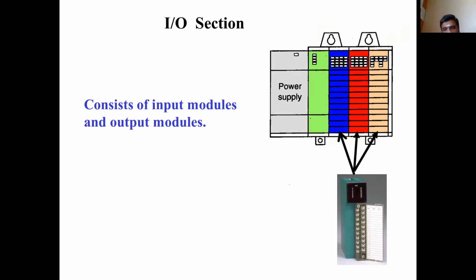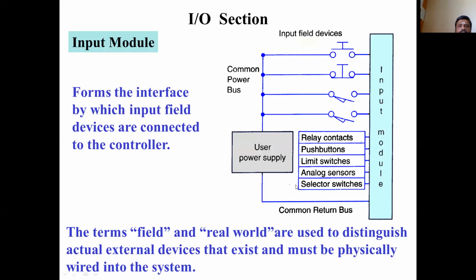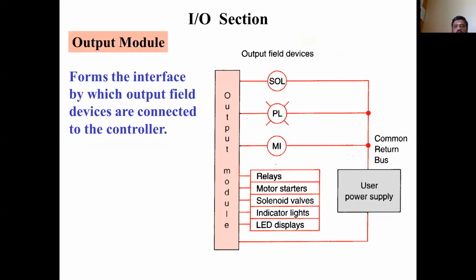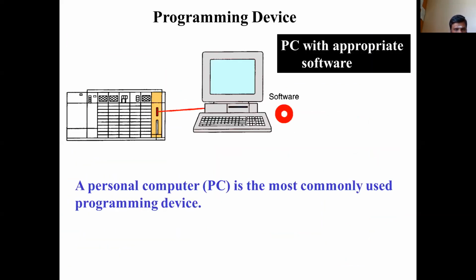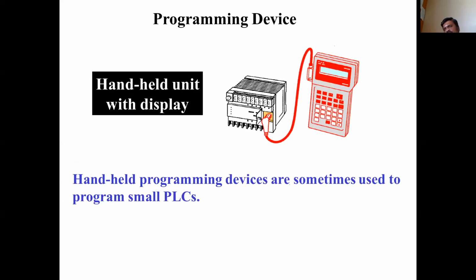Then this is the typical input-output module. Here you have the input and output modules that you can connect devices to. Things that can act as inputs are a relay contact, a push button, an analog sensor, or a selector switch, any input. Then you have the output module. As we already mentioned, relay, solenoid valve, indicators and LEDs act as the output devices. Other than a computer, we can also use a handheld unit as a programming device so that you can program the PLC.